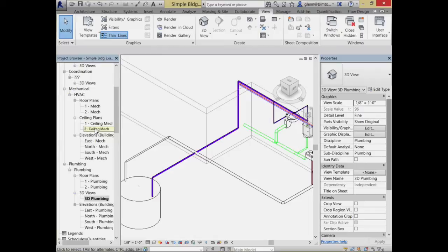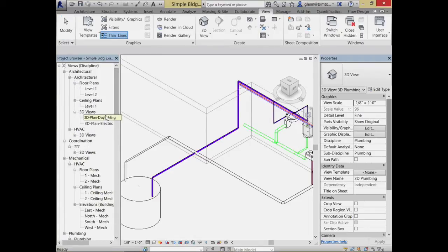Final piping thing I want to show you, just so you have a complete understanding of one more system that is very useful to include in your building, is sprinklers. Sprinklers turn out to be a really easy thing to do, because if you think about where they're located, they tend to be up in ceilings, in the center of ceiling panels and stuff like that. The precise spacing of where they need to be placed is based on the amount of pressure behind each of the different sprinklers and what the flow is of the sprinklers. So there are formulas for figuring out, for an amount of pressure, the radius that can be covered and how much overlap you want to have between them all to make sure that everything can ultimately get doused with water as needed to suppress the fire.